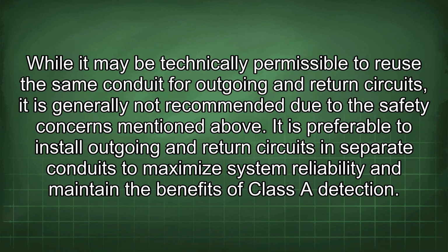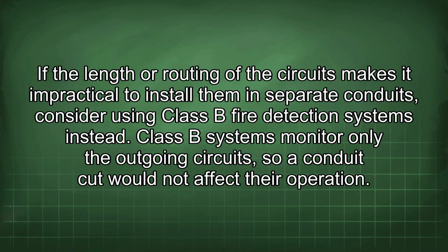While it may be technically permissible to reuse the same conduit for outgoing and return circuits, it is generally not recommended due to the safety concerns mentioned above. It is preferable to install outgoing and return circuits in separate conduits to maximize system reliability and maintain the benefits of Class A detection. If the length or routing of the circuits makes it impractical to install them in separate conduits, consider using Class B fire detection systems instead.